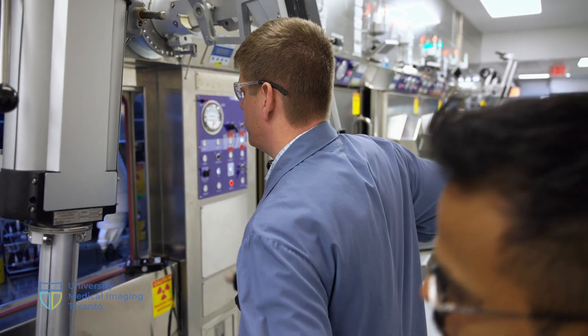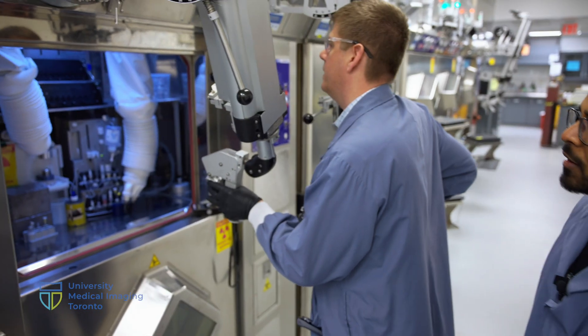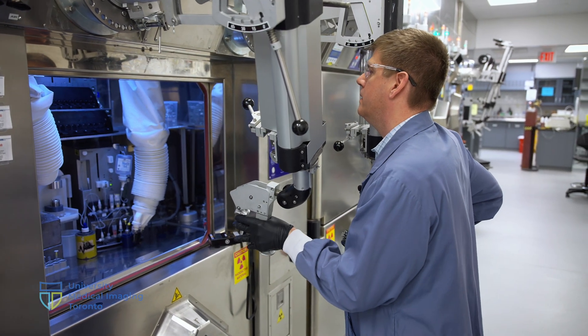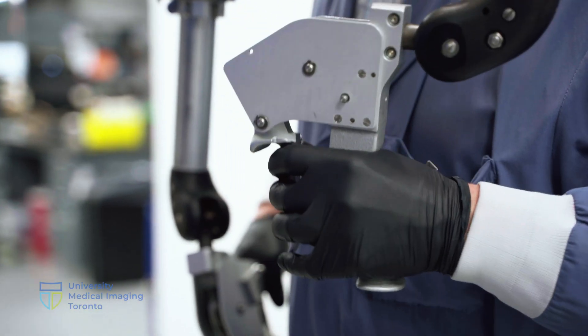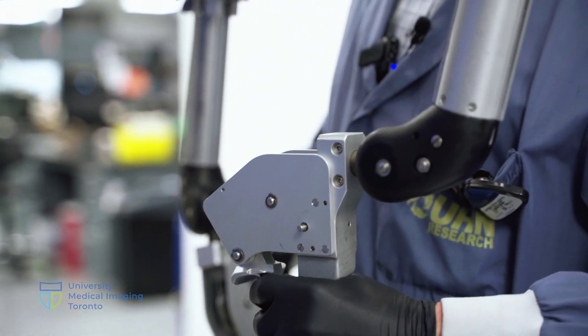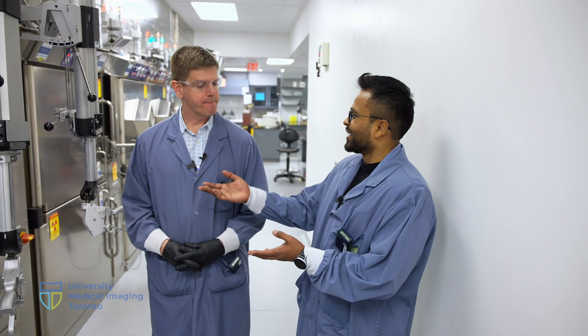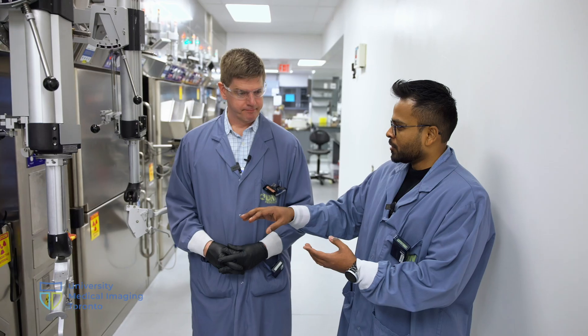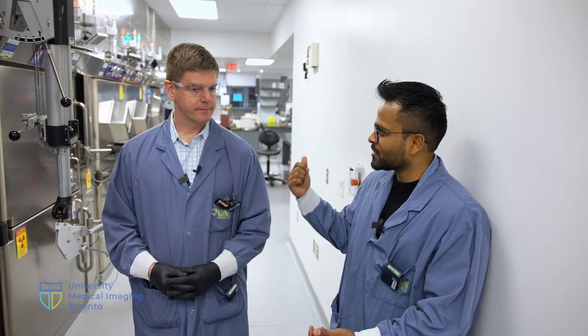In this case we would use this manipulator arm and grab the coin here, place it in its position, and we already have one in the spot — and that would dissolve it. So that is how radioisotopes are created. From the cyclotron to here via pneumatic tubes — but how does this get from here to the patient waiting upstairs for the scan?